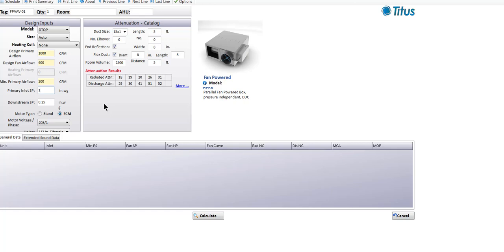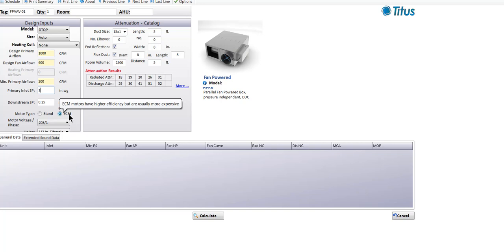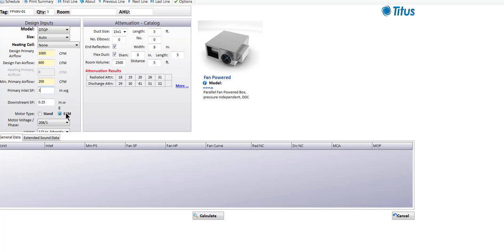We're going to put our inlet static pressure back up to one inch, because this parallel box does not boost the air handler — the air handler has to move the air to the box, through the box, and all the way out to the room. Although we offer the ECM option on parallel fan boxes, depending on where this box is operating, it might be a long payback. Most people are going to go with a standard PSC fan motor for a parallel fan box — in South Florida, for instance, you might never run the heat enough to ever get a payback on an ECM.